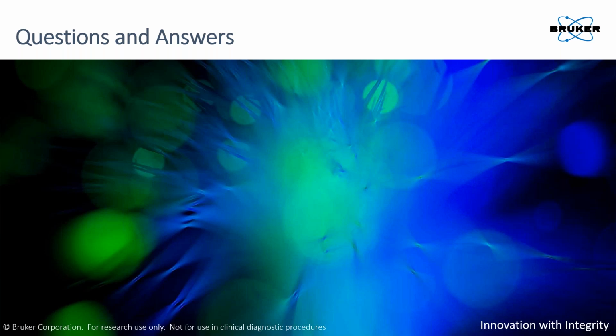But what is also interesting, even if you do not have standards for a new compound you would like to add, you can still run them as a suspect, meaning that having information just on molecular formula of the compound is sufficient for the instrument to run and provide some data on presence of these compounds in samples, obviously with no information on retention time. So identification confidence will not be as high, but it's still possible to perform this, what we call screening for suspects, having only molecular formula to go by.